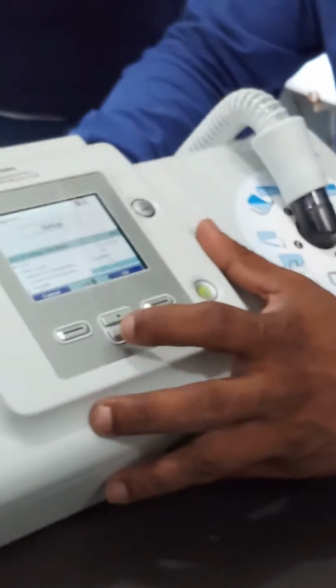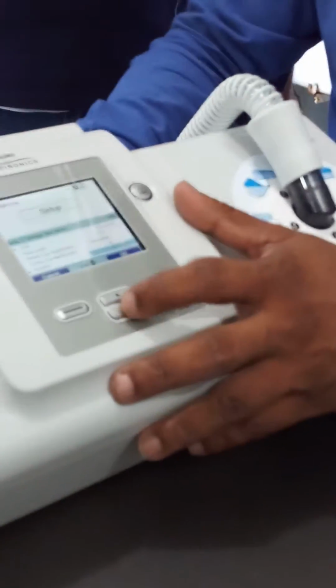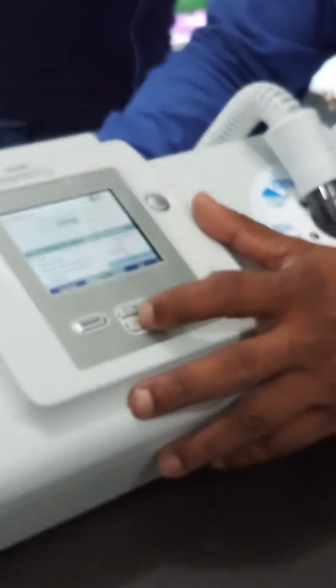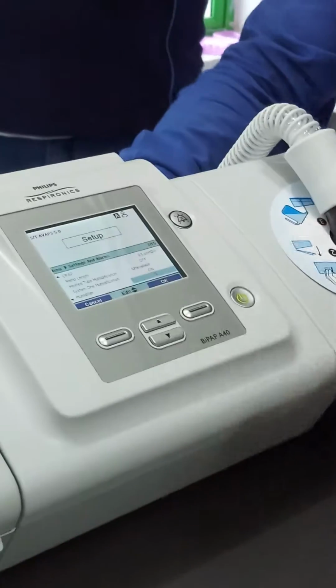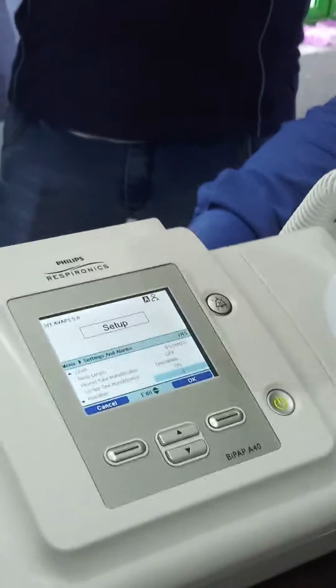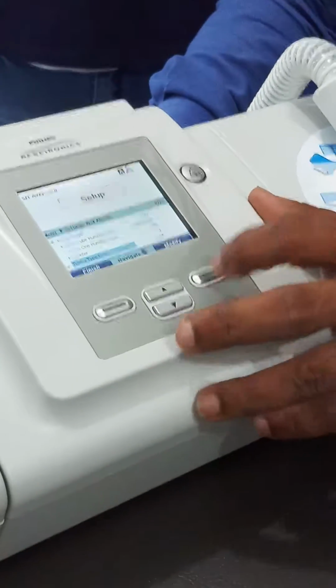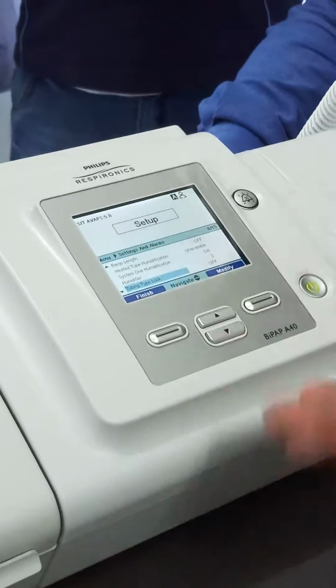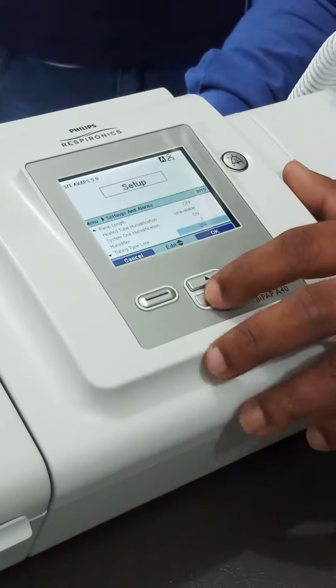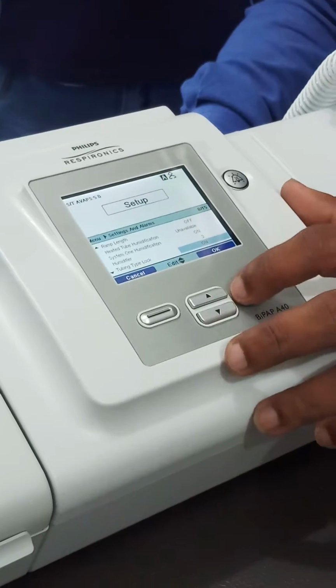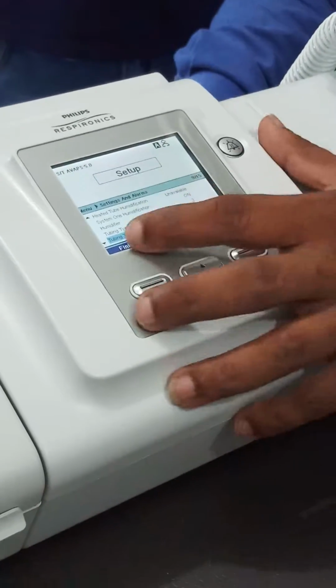Better to keep it not at zero. Why? Zero means no humidification, so it has no effect. Five is the best. You can keep it at 2, 3, 4, whatever the patient's situation needs. If it is a pediatric patient, you can put it at 1. And the tubing type, when a pediatric patient comes, hold on.